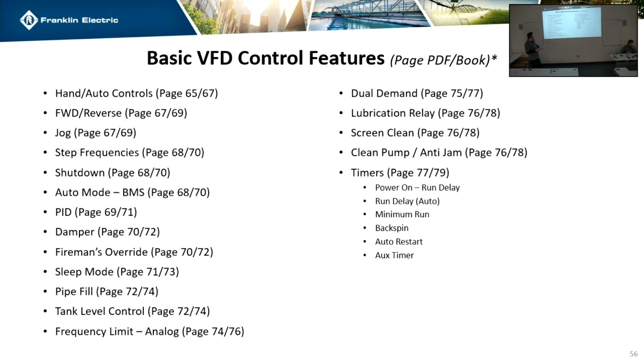Let's see. What's that for, like if you tied in a duct detector or something? Yeah, anything that they want tied into it that's going to shut it down, that's what that's for. The fire code would be like the duct detection, but you can use shutdown for anything. I mean, you could have a proximity sensor that if someone gets close enough to the drive, it just shuts it down.